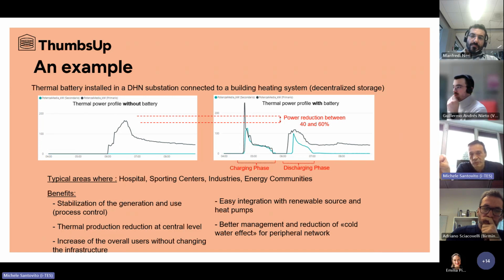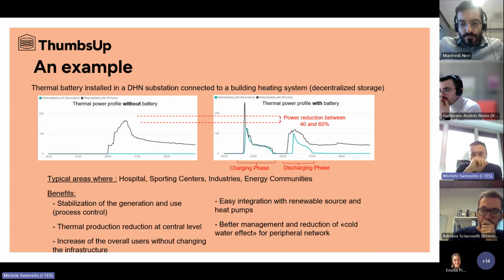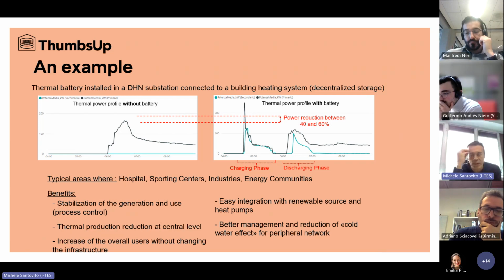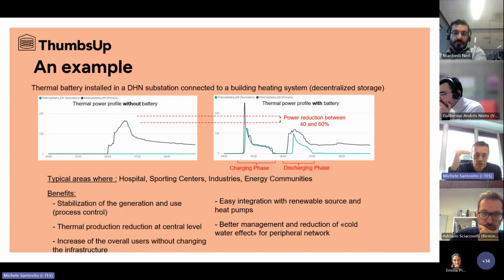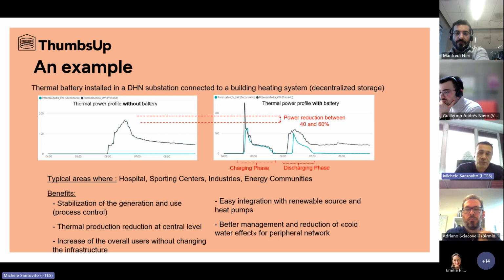An installation on the building, directly on the building in its substation. We use this kind of storage as decentralized storage, far away from the central one, where there is a very big, large water tank in order to keep the process in control, from a thermal point of view but also from the pressure point of view. But if you work closer to the user, the efficiency will rise and grow in a very impressive way.